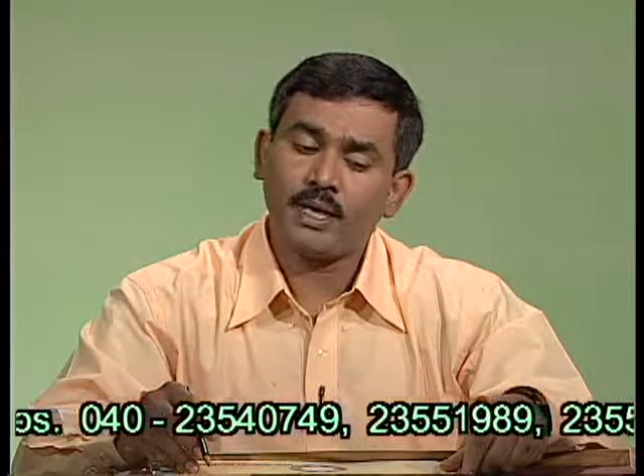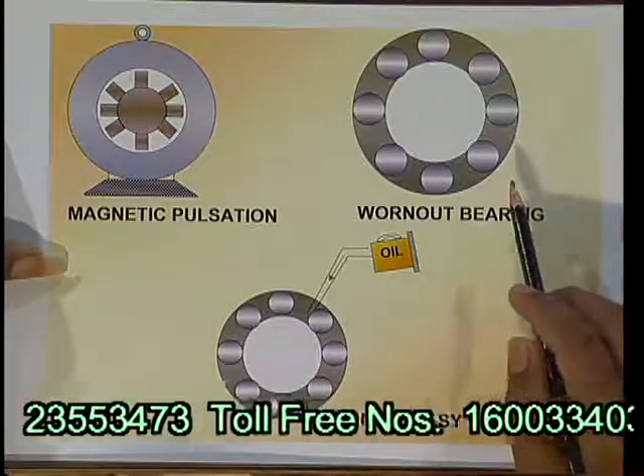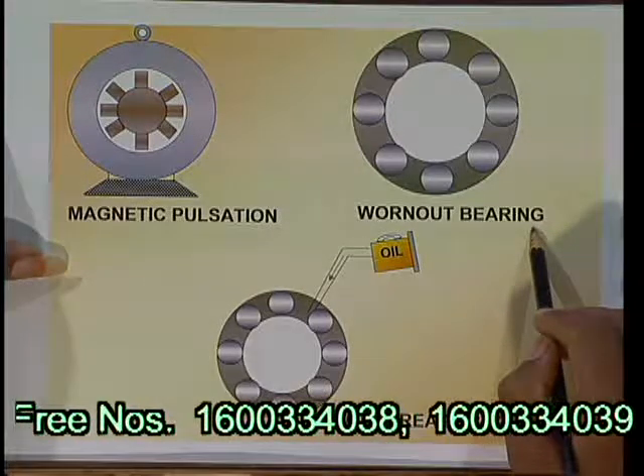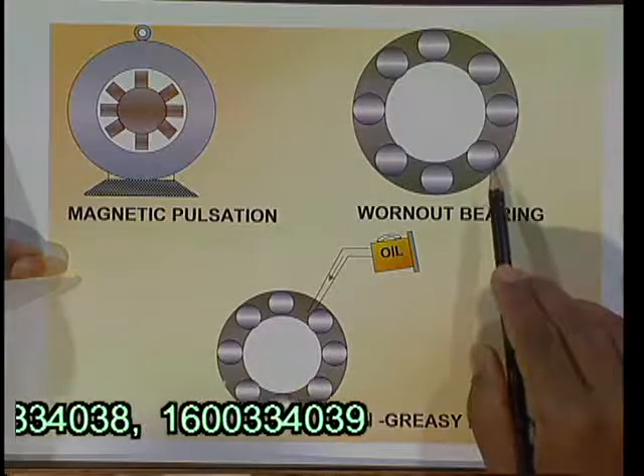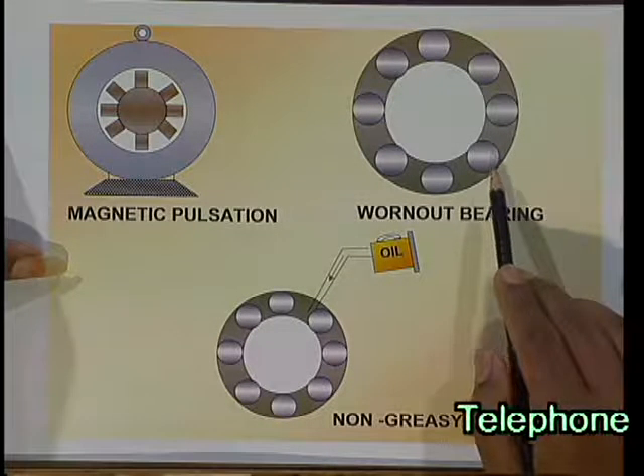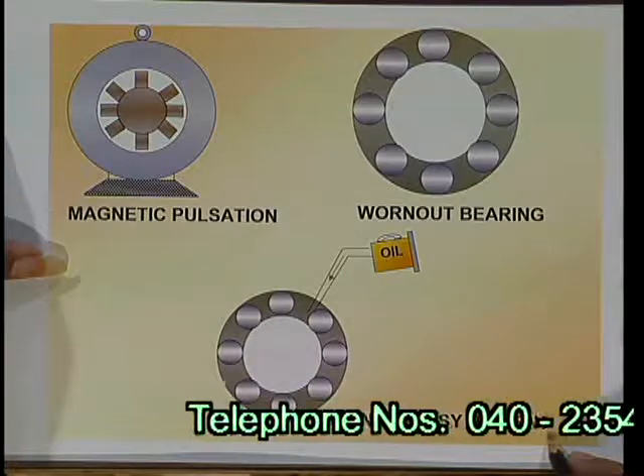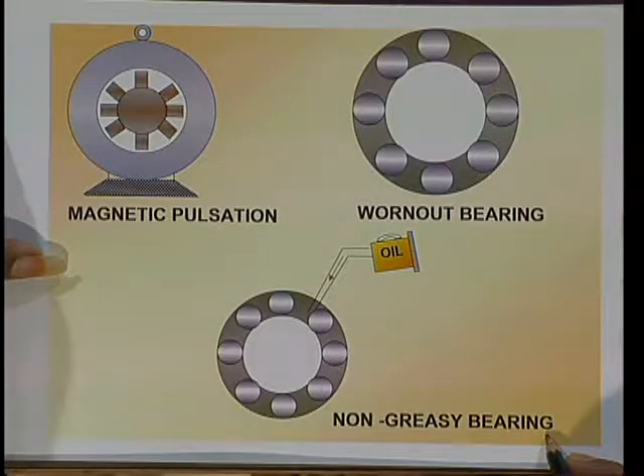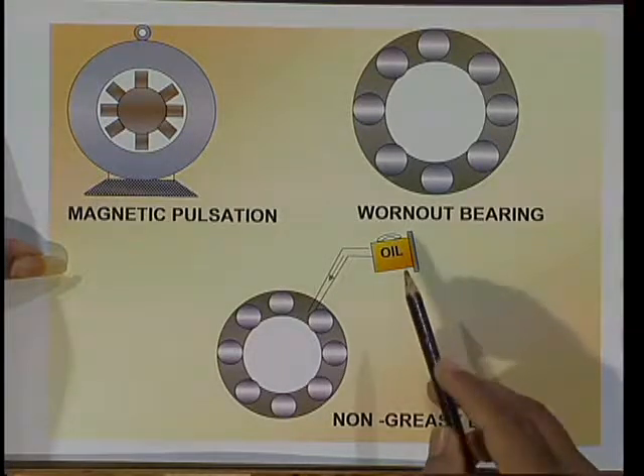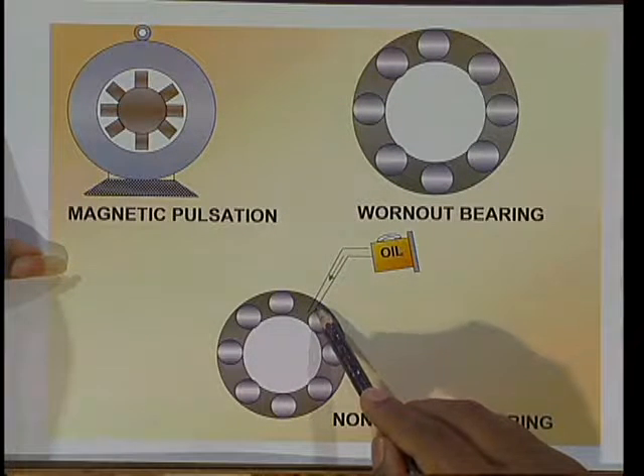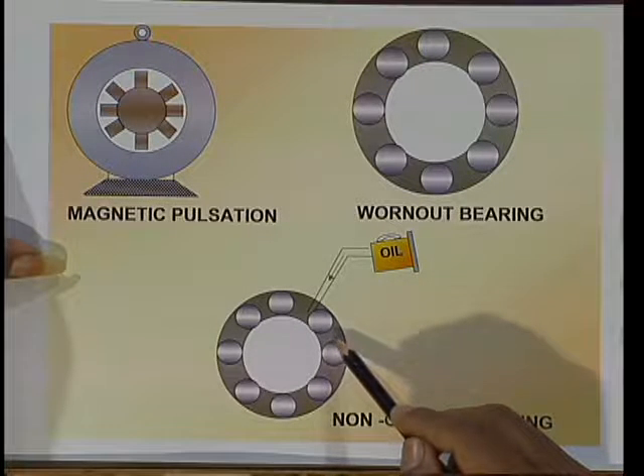Noise due to magnetic pulsation can be reduced by selection of the correct number of slots. Noise due to worn-out bearings can be reduced by replacing the bearing with a new one. Noise due to non-greasy bearings can be reduced by pouring oil or replacing the old grease with new grease. These are some reasons for production of noise and the methods for reduction of noise.